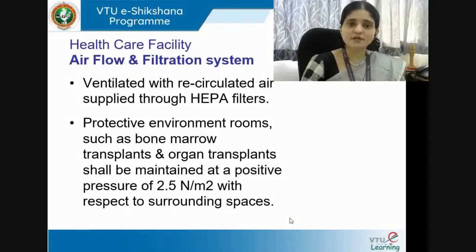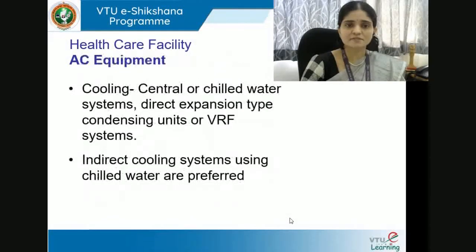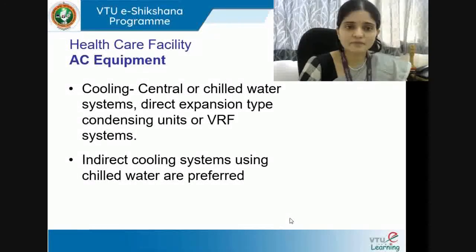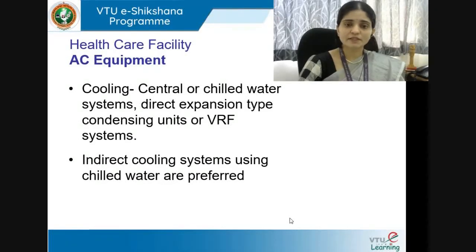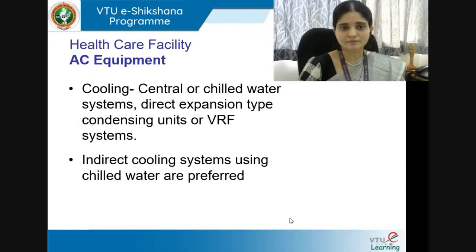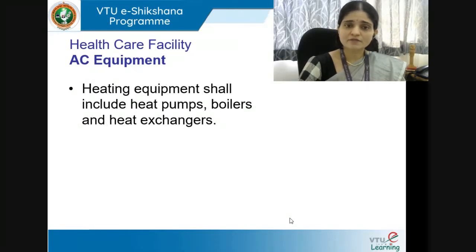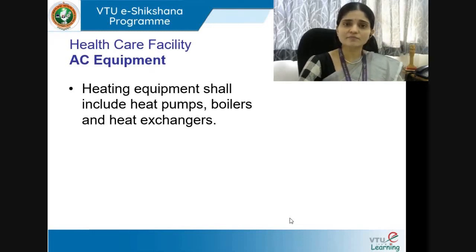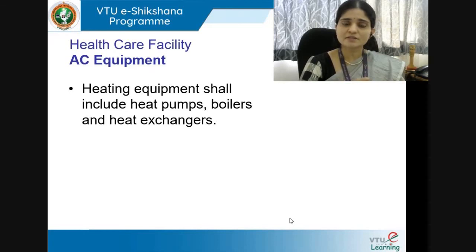These facilities should be ventilated with recirculated air supplied through HEPA filters only, which provide 99.98% efficiency. Protective environment rooms such as bone marrow transplant and organ transplant rooms shall be maintained at a positive pressure of 2.5 Pa with respect to surrounding spaces. For AC equipment, cooling shall preferably use central or chilled water systems. Direct expansion type condensing units or VRF systems can also be adopted — these were covered in detail in module 2 section 3. Heating equipment shall ideally be heat pumps, boilers, or heat exchangers. Selecting the right equipment with the right capacity to serve requirements is important.